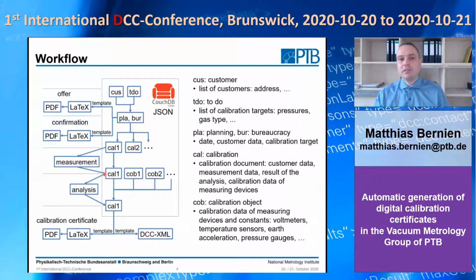During the analysis, information is needed on the calibration data for the devices used for the measurement. That is collected from the database from so-called calibration object documents that are then merged into the calibration document, so that all the data that was needed for the calibration is contained in this one document. Then from here, the calibration certificate is generated through the template system, first making a LaTeX file that is then compiled to PDF, and through the same template system, the XML file for the digital calibration certificate is generated.